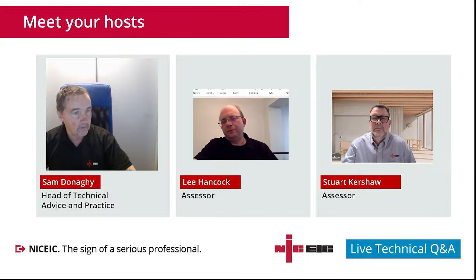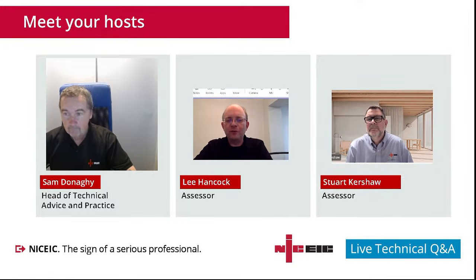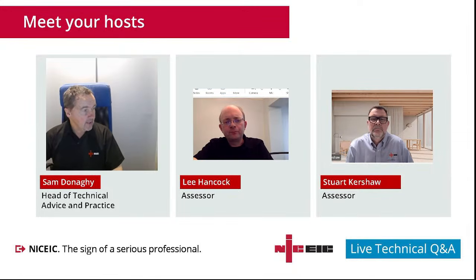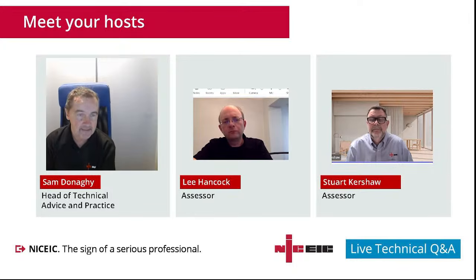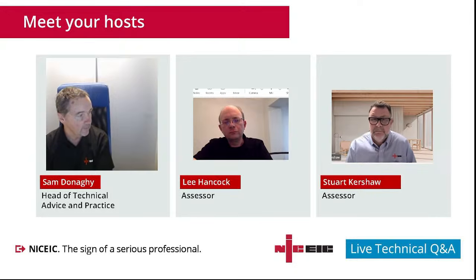We'll dig into that, and if not at the next session, perhaps in a social media post or in one of the connections articles, do something that covers around that, because it is something that I've seen before. This one's referred to. The electronics within the equipment themselves are introducing this impedance that in reality doesn't exist. Yeah. Another engineer tonight has said that in terms about aging a cable, flexibility of the cable is a good indicator. Yeah, I think we'd all agree with that, but sometimes you can't actually demonstrate that if it's in containment or if it's in the fabric of the wall. So although we agree, it's not something we can often do.